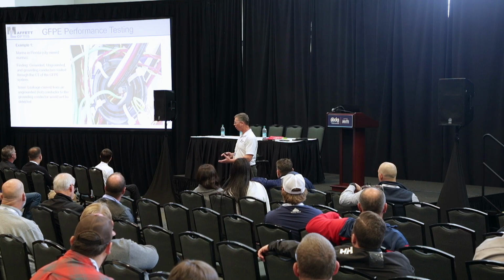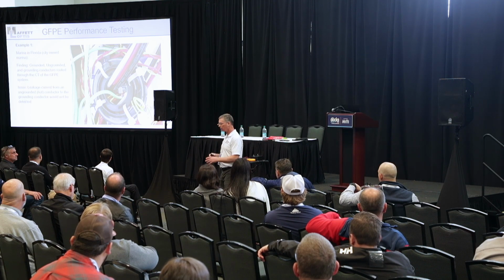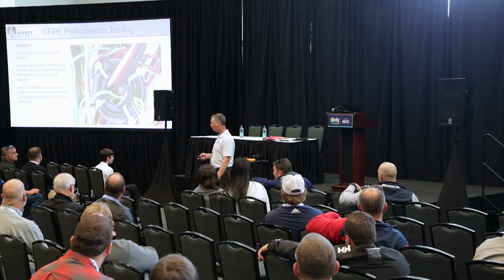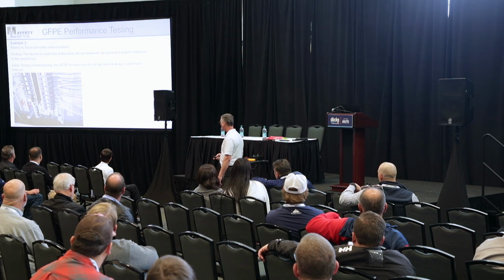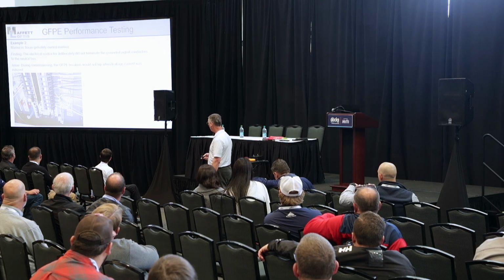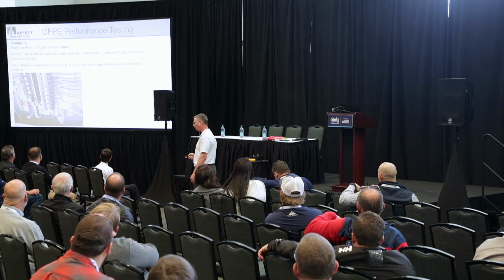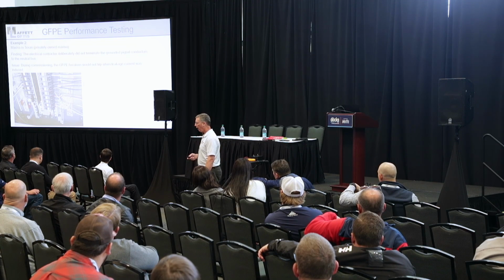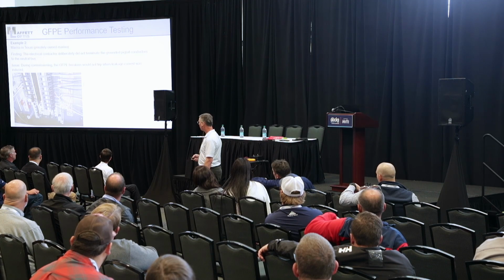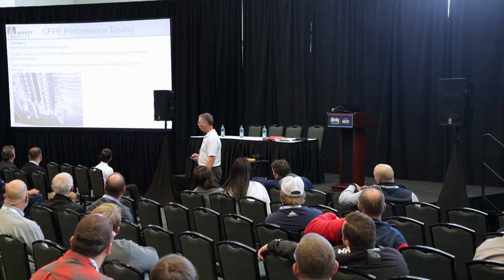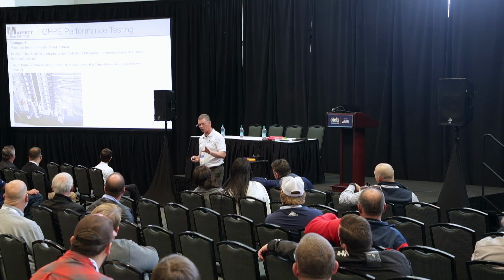Here I could leak whatever current I wanted and it would never trip, ever. And the inspector passed this. This was a problem at a marina, and the electrician tried to actually cut some corners and wired, and this was my design, but these are GFPE breakers, tried to wire these up with sharing neutrals on GFPE breakers. You can never share a neutral on a GFPE breaker.